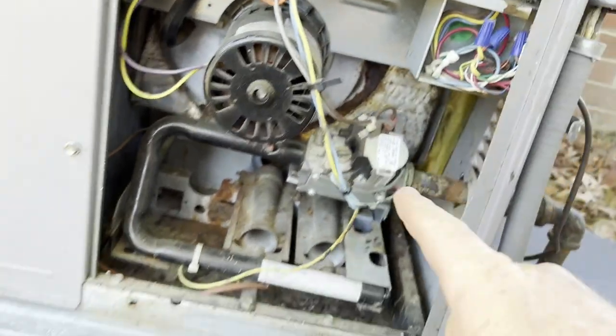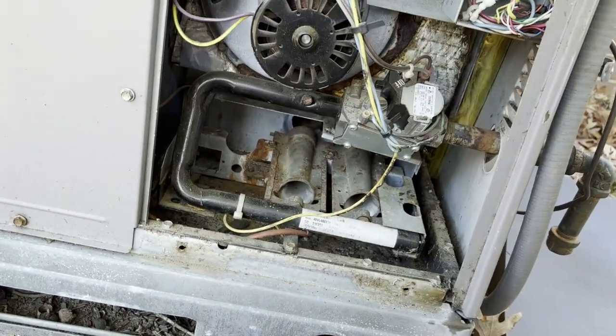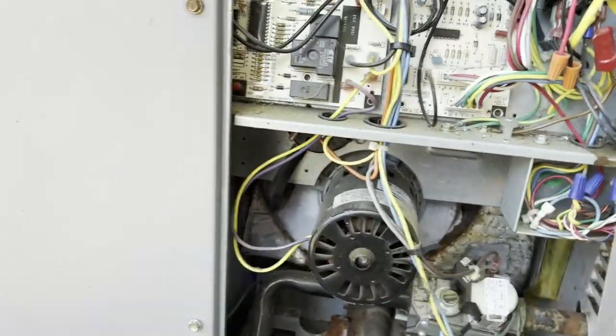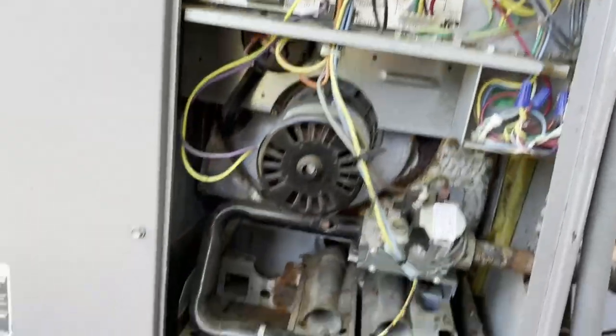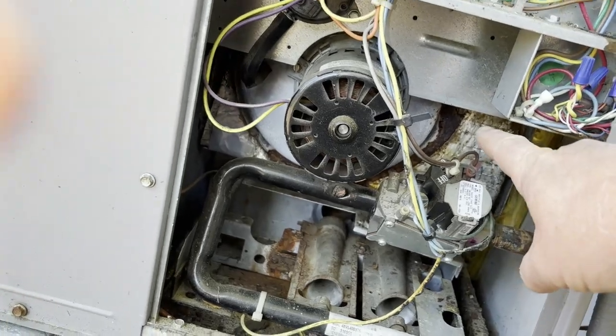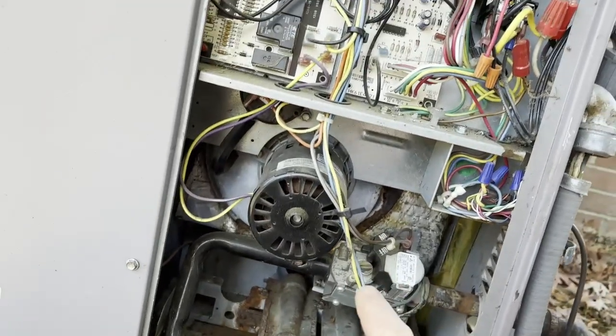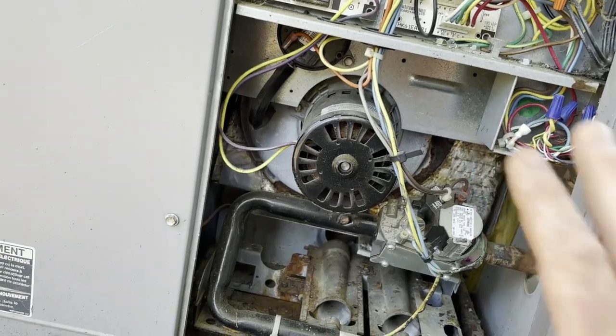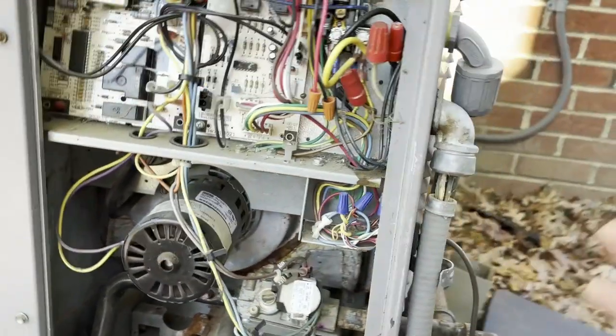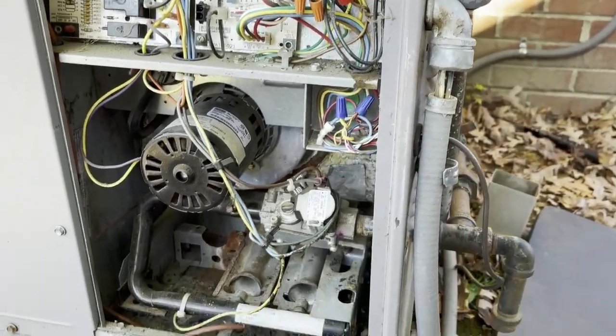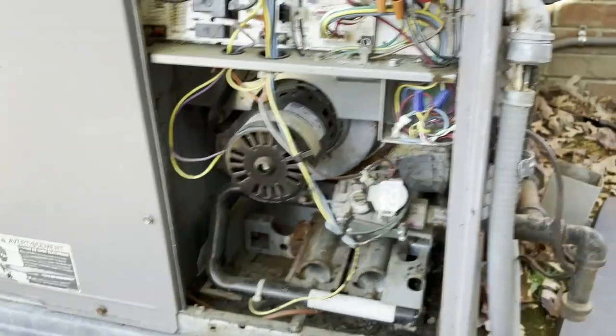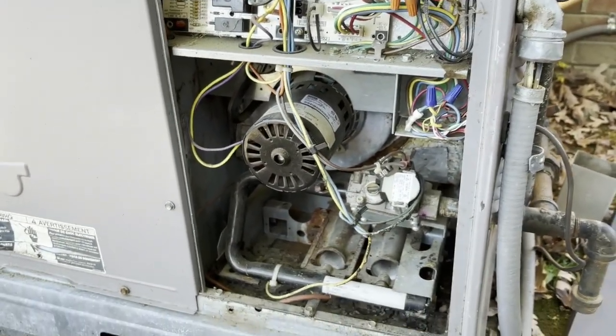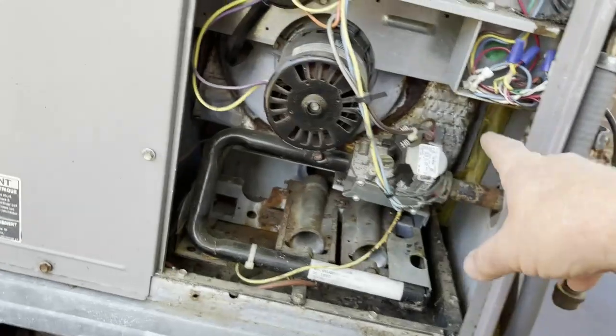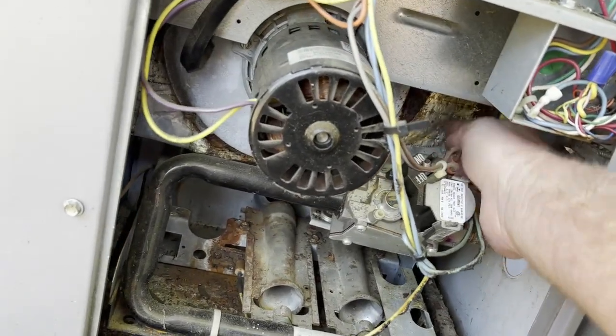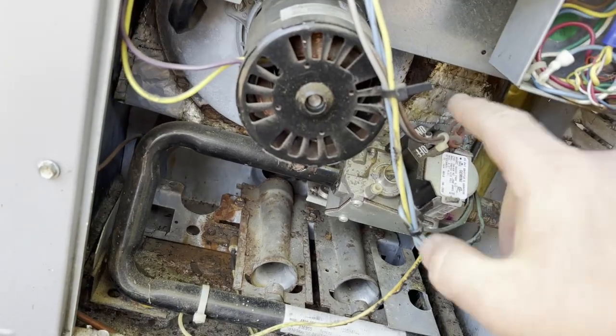And a word of advice on these units, this particular one, with this design, whether it's Tempstar or Carrier or Payne, Bryant, whatever it is, there's a panel that sits behind this draft motor that mounts to the front of the heat exchanger. So if you ever show up on one of these and find a cracked heat exchanger and they want to fix it, that's fine if it's not extremely old, it's their option. But if you're going to order the heat exchanger, make sure you order this faceplate panel back here that fits over the front of it.